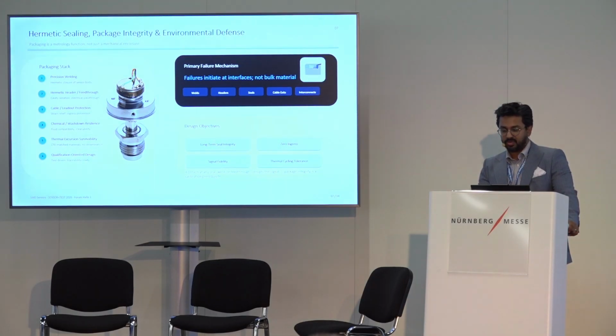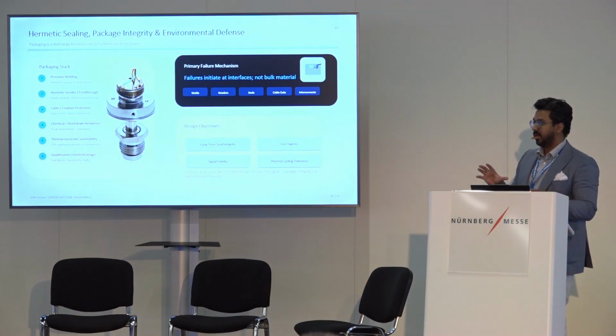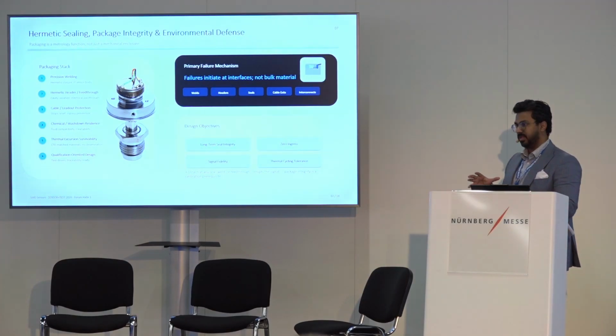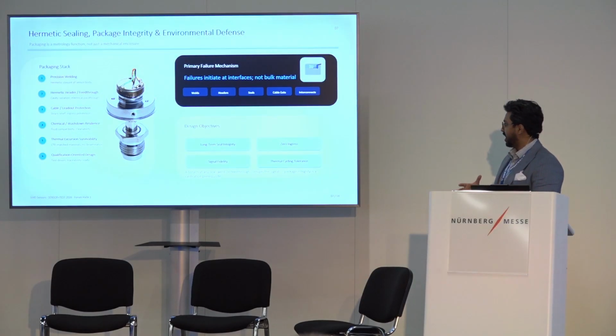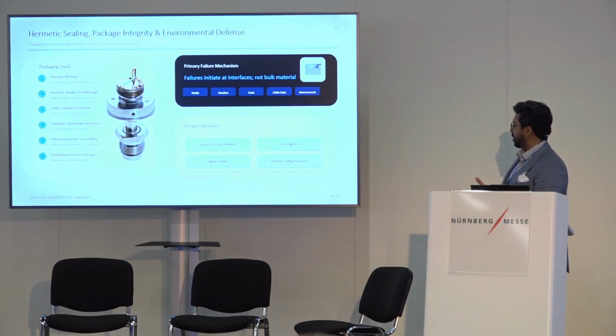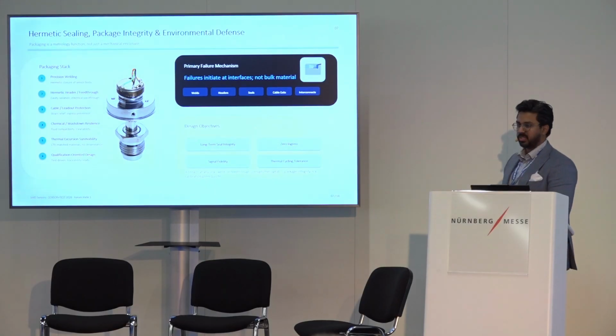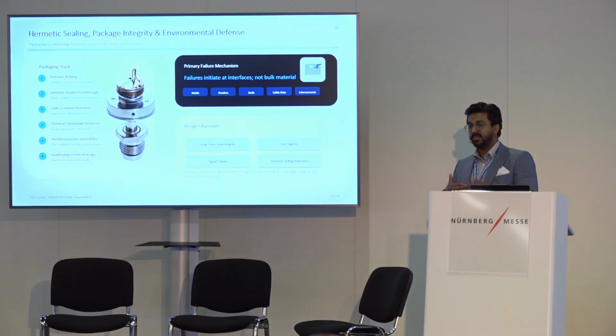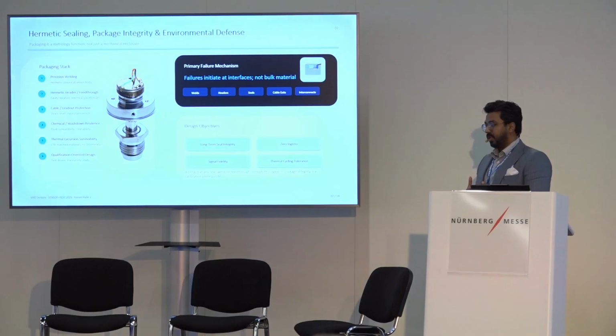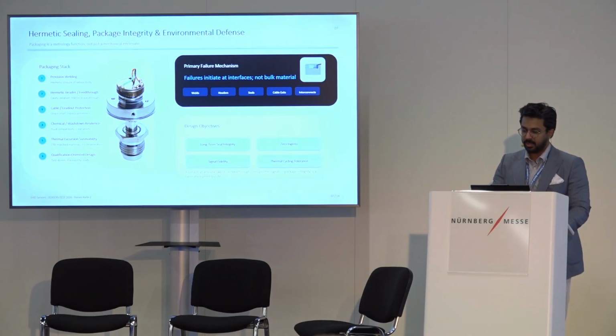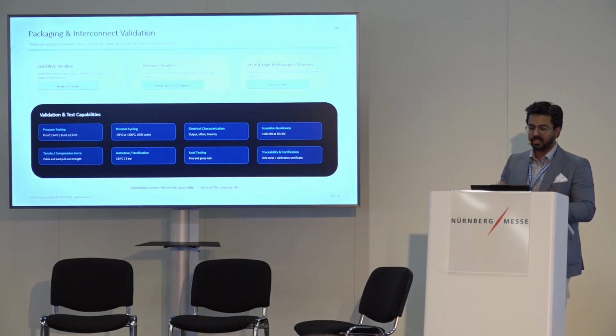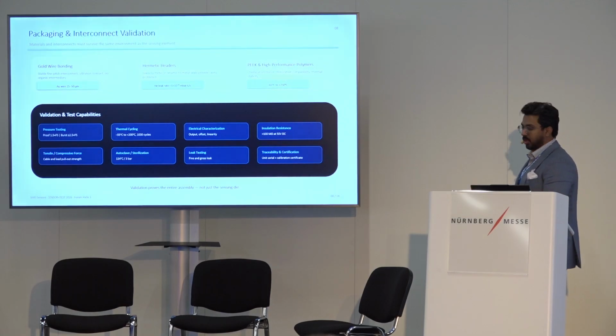To do that, we do a lot of testing and have design objectives we have to set up. We run tests around long-term seal integrity, zero ingress, which I've talked about, and signal fidelity too, while doing thermal cycling and fatigue testing on these sensors. Next, we'll talk more about the full validation of this sensor packaging and interconnections.